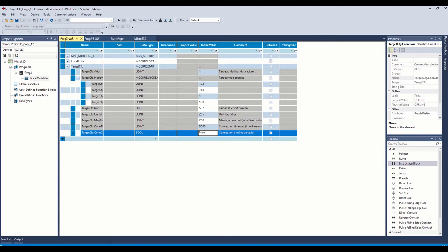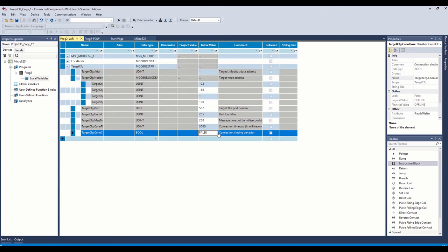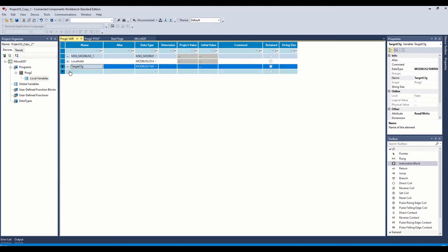If you look in the programming manual, it describes this whole word, gives you a description of each one. And this connection closing behavior is used after the message instruction executes, do you want to close the connection? And I guess you could save on the Ethernet network if you wanted to do that and you were only doing this once a day or once every hour, once every five minutes, something like that. But if you're going to sit there and read constantly, you want to just put that at false and let it do that. So that one's set up.